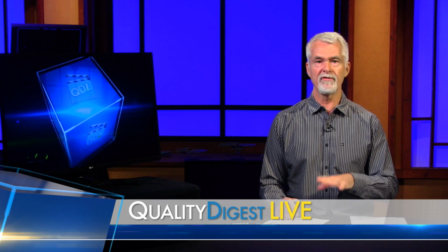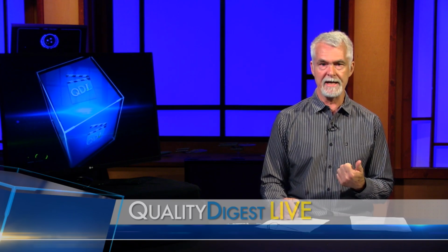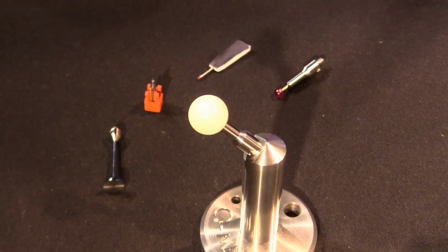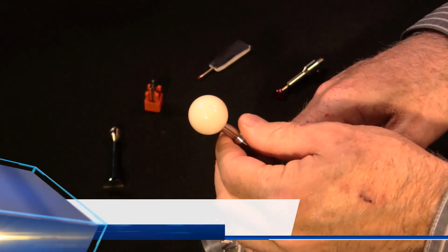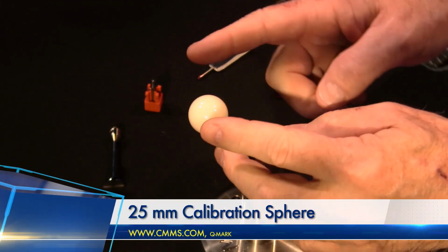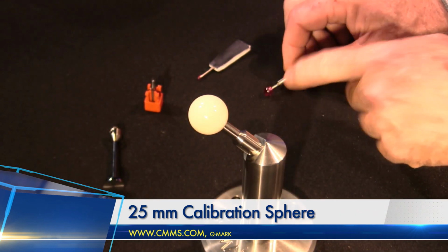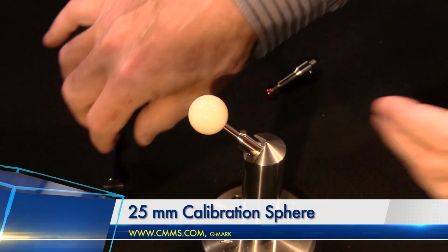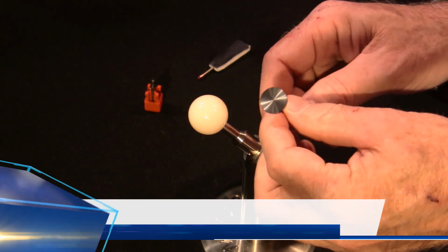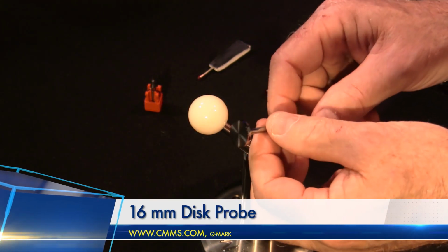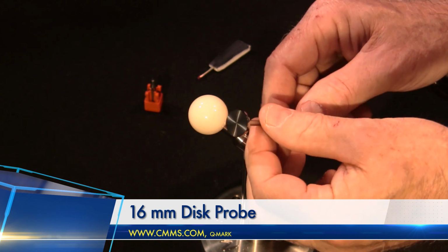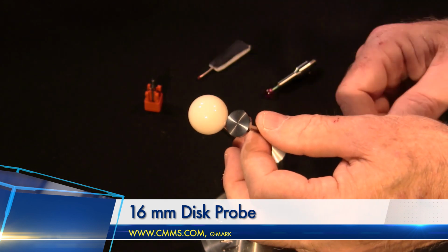And we're going to look at a few of those products here today. We're going to look at a couple of different calibration spheres and 3 different probe types that are sold by QMark, and how you would calibrate these probes using the calibration sphere. So if we can just switch over to our gauge cam here. Okay, so what we see in front of us here is a couple of calibration spheres, a 25 millimeter calibration sphere, an 8 millimeter calibration sphere, and a couple probes. And the first thing we're going to look at is an off-the-shelf from QMark disc probe here. I'm going to show you how you might calibrate a disc probe using the 25 millimeter calibration sphere.